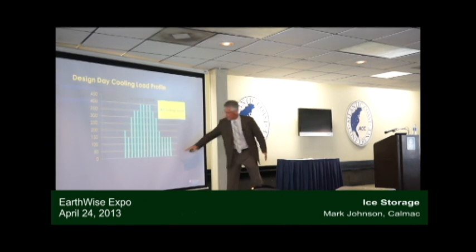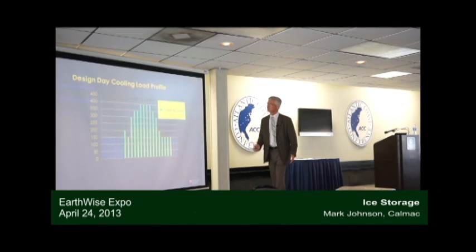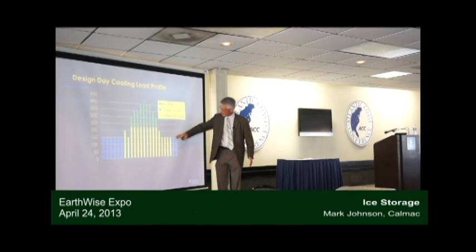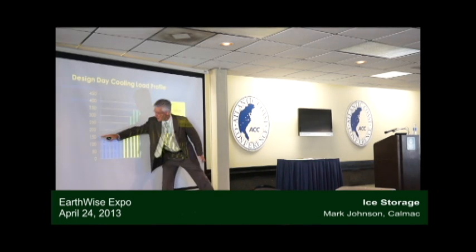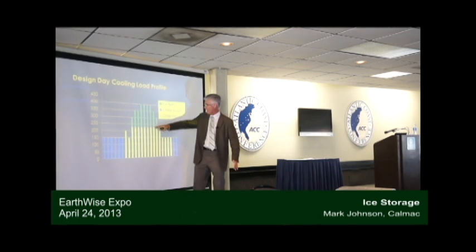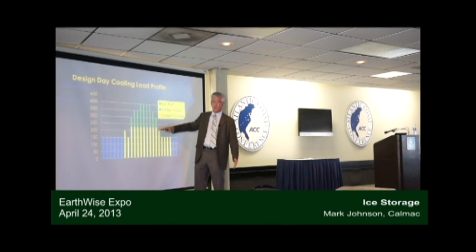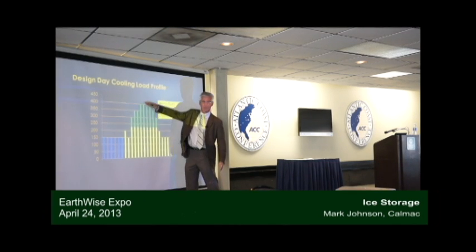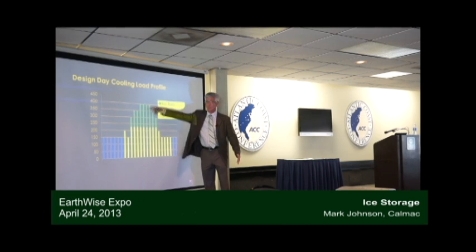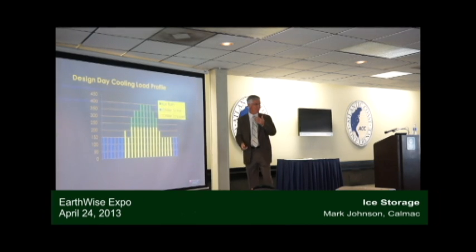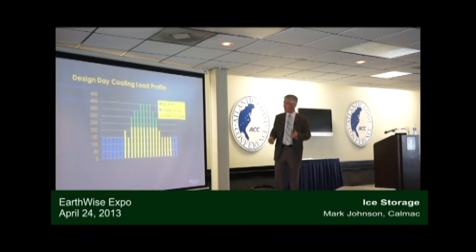Everything gets shut down around 10 p.m. With thermal storage, what we're trying to do is run our chiller over here, and then have it run flat loaded all day. This is partial storage. And they're going to have the ice get this load. Why? That's the most expensive power, right? I can sort of beat that dead horse pretty hard.